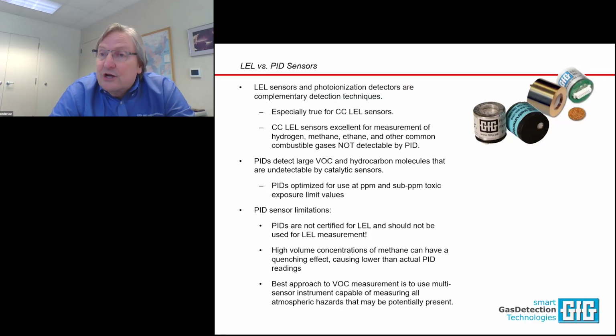LEL and PID sensors are complementary detection techniques. That is especially true when the instrument is equipped with catalytic LEL sensors. Catalytic LEL sensors are excellent for the measurement of hydrogen, methane, ethane, and other common combustible gases that are not detectable by PID. PIDs, on the other hand, are excellent for measuring toxic VOCs and larger hydrocarbon molecules that are less detectable by combustible catalytic LEL sensors. And PIDs are optimized for use at ppm and sub-ppm exposure limit ranges.